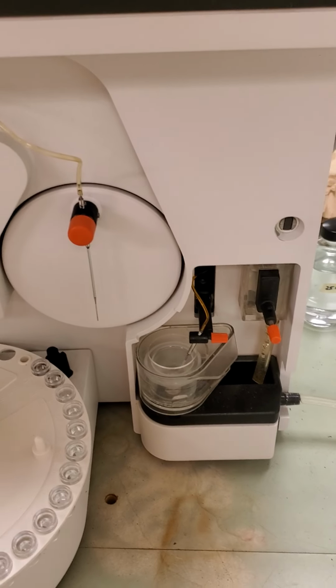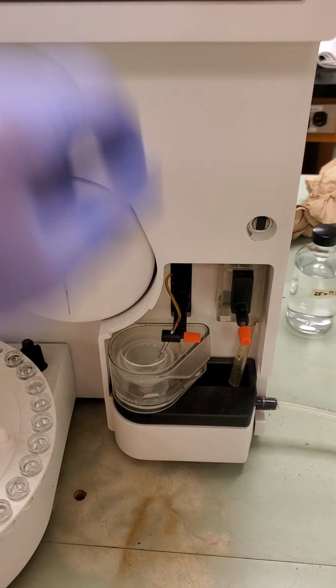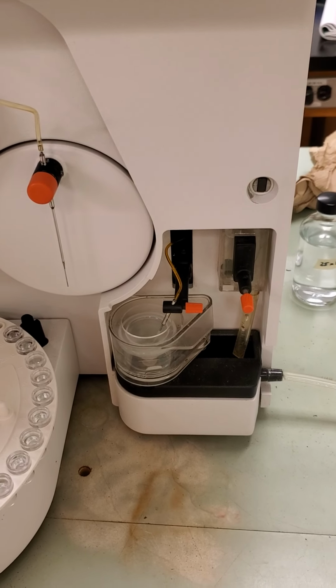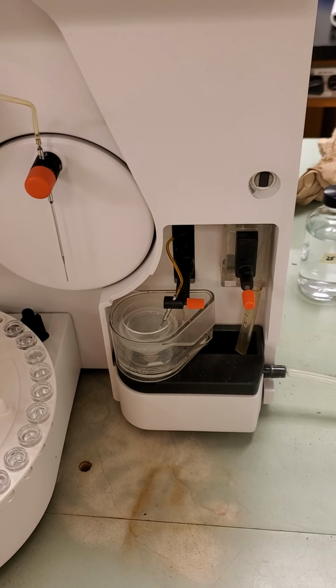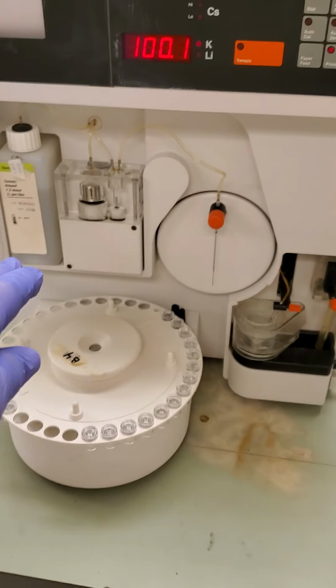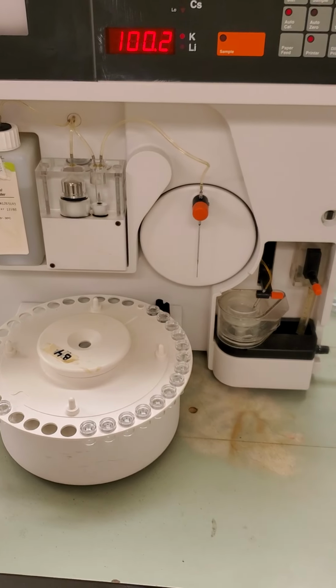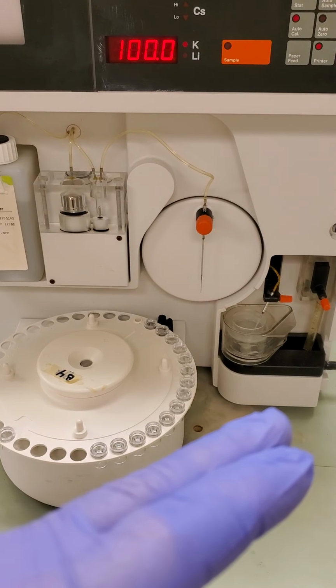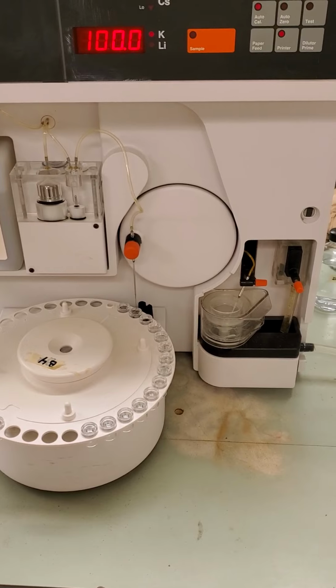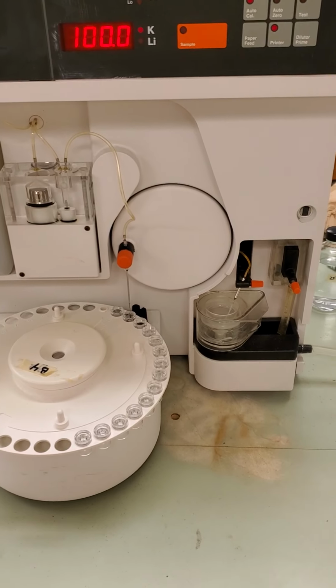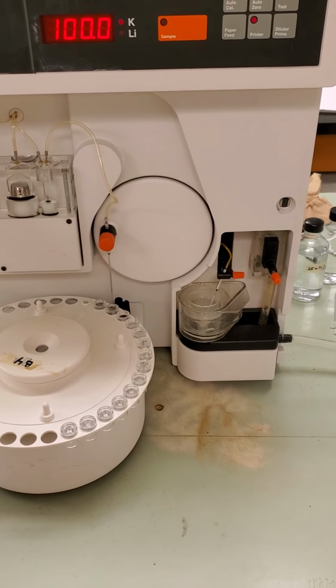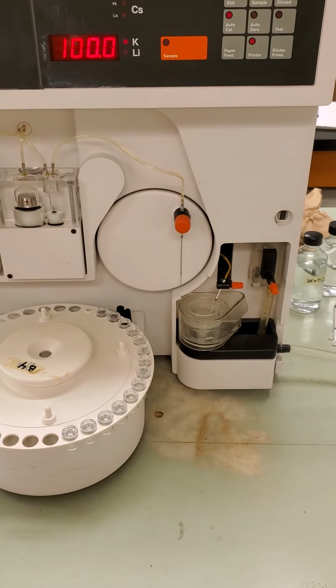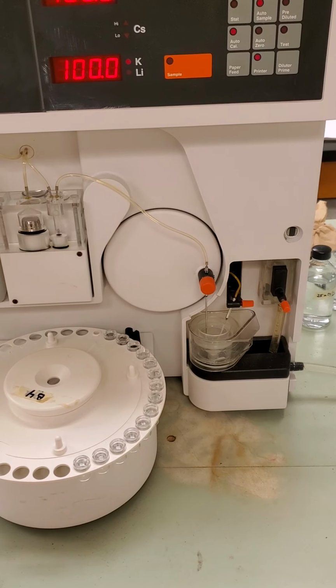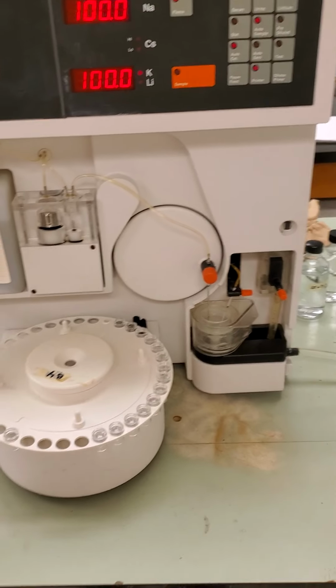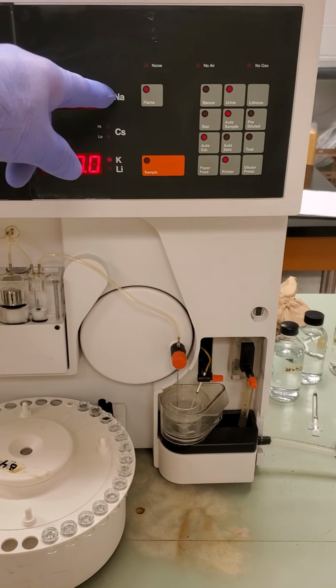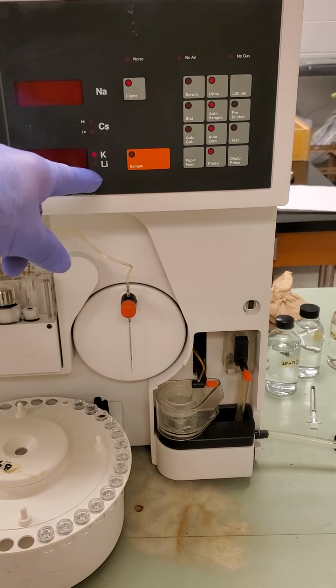Now this system obviously, the sample feed is going to be irregular because it's using aspiration. The way it normalizes the readings is the cesium diluent. So the cesium diluent, which nobody should have in a urine sample, is used by the machine to normalize each reading, to know what quantity it's actually testing. So when it burns the sample in the burn chamber, it has 4 sensors around the perimeter of the chamber, and each sensor measures a different frequency of light. So one will measure sodium, which is a yellow light, cesium, potassium, and lithium.